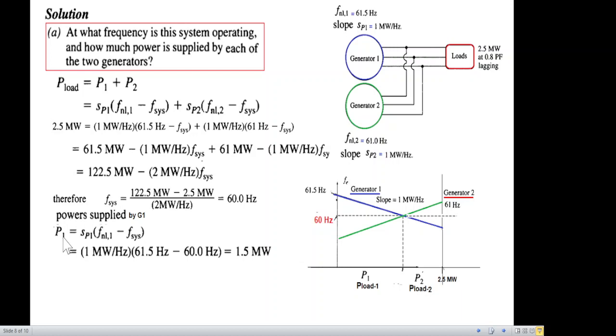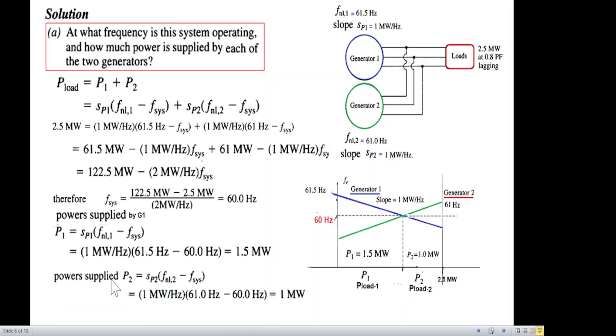Now that we know the system frequency is 60 Hz, we calculate the power supplied by each generator. Using the power formula with f_system = 60 Hz, generator one is supplying P1 = 1.5 MW and generator two is supplying P2 = 1.0 MW. The sum of the two equals the total load of 2.5 MW.